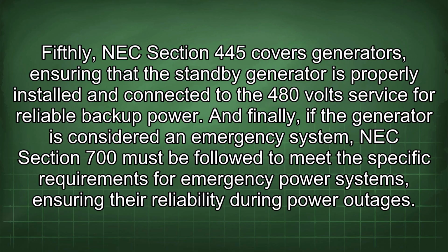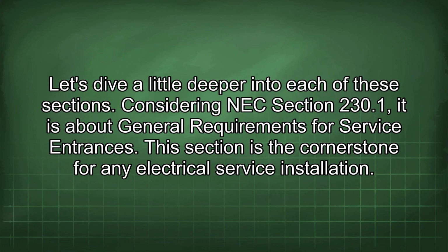Fifthly, NEC section 445 covers generators, ensuring that the standby generator is properly installed and connected to the 480-volt service for reliable backup power. And finally, if the generator is considered an emergency system, NEC section 700 must be followed to meet the specific requirements for emergency power systems, ensuring their reliability during power outages. Let's dive a little deeper into each of these sections.